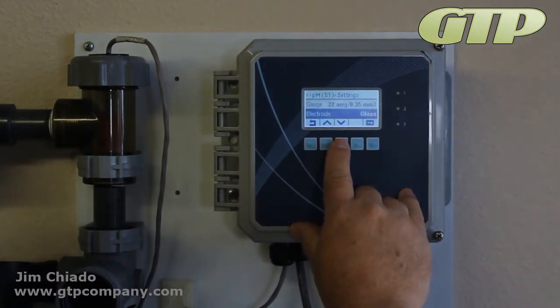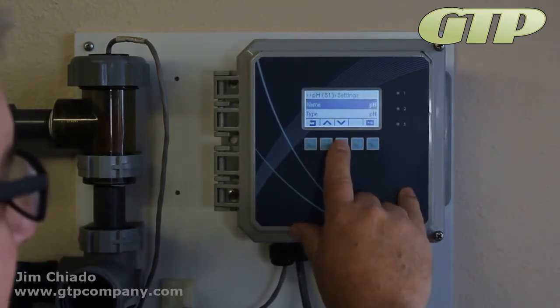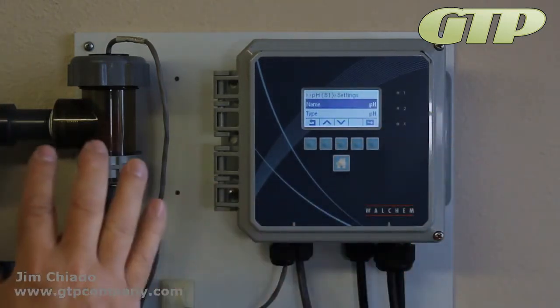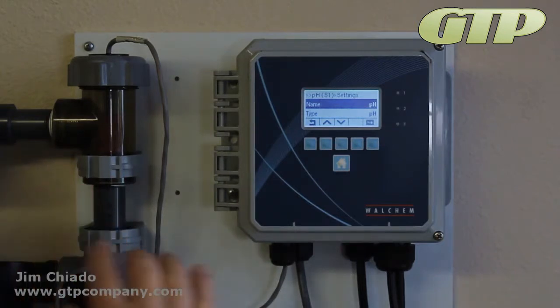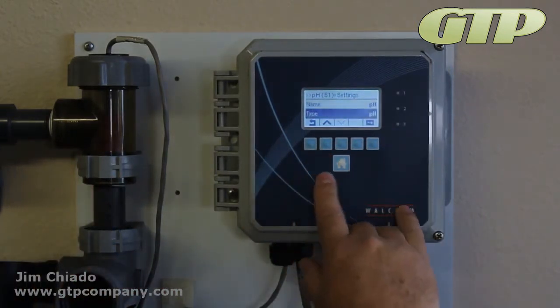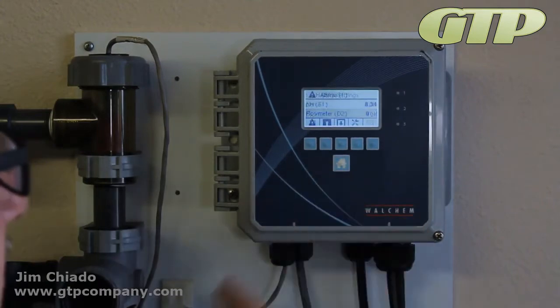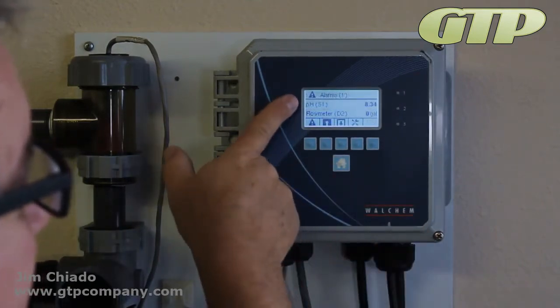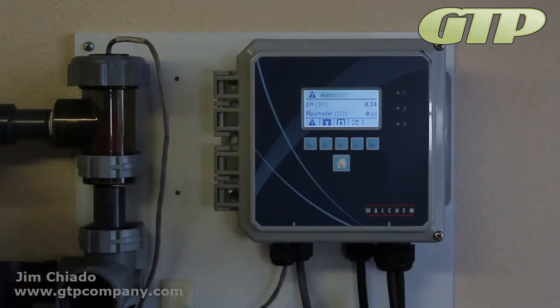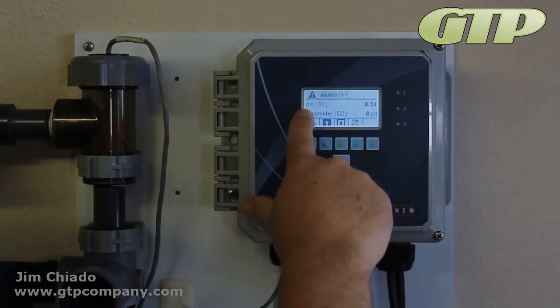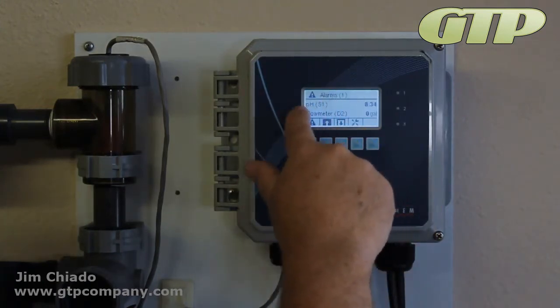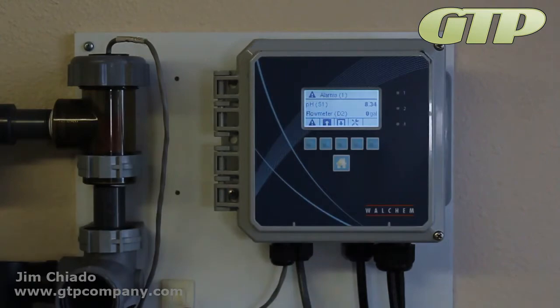That's a 22 gauge, electrode is glass. The name is pH, you can change it. Maybe this is tower pH or something like that. And then the type is pH. pH is configured. Now you can see that it automatically changed it because the display setting was S1. Whether it's conductivity or pH or whatever, it's still S1. It will show up there on the home screen.